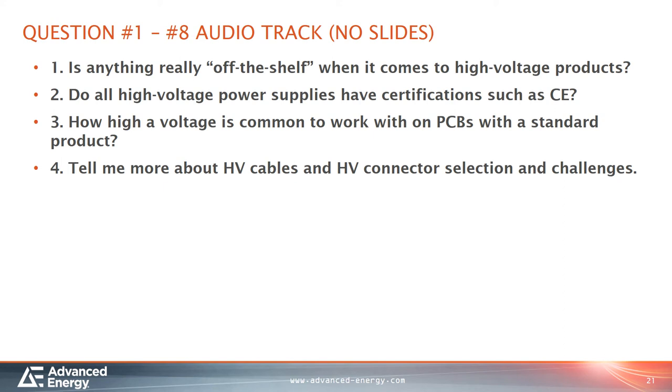And coaxial, of course, is a very common type of shielded cable. Its field stress characteristics are not as good as the triple extruded semiconductive coating we just talked about. However, it is very effective in low noise applications and applications where shielding is important, but also adding stored energy for additional filtering is also important.